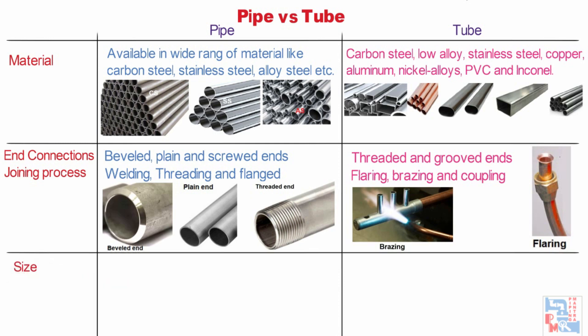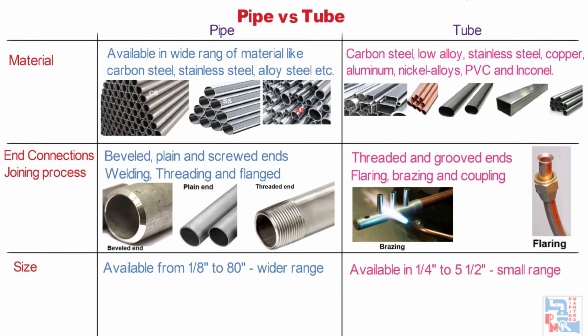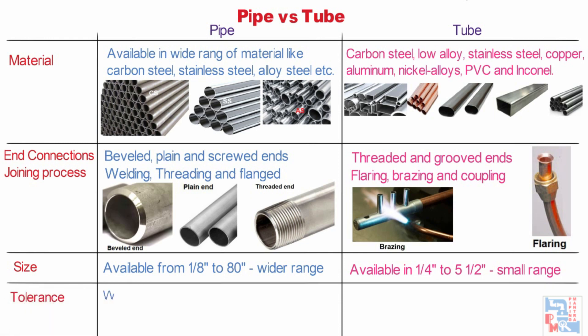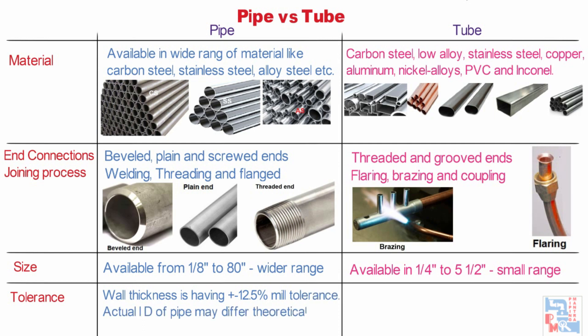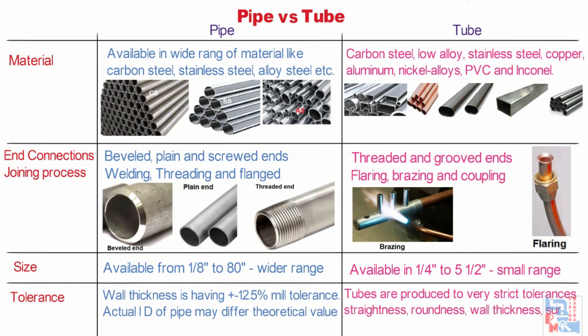Now we will talk about size. Pipes are available in a wide range from 1/8 inch (0.125 inches) to 80 inches, whereas tubes are available in a smaller range from 1/4 inch to 5.5 inches. Regarding tolerance, pipe wall thickness has ±12.5% mill tolerance, so the actual ID of a given pipe may differ from the theoretical value. In the case of tubes, steel tubes are produced to very strict tolerances and undergo several dimensional quality checks such as straightness, roundness, wall thickness, surface, etc. during the manufacturing process.